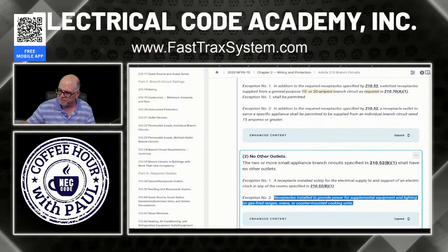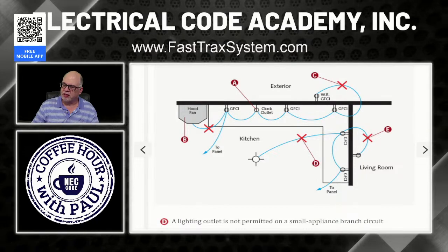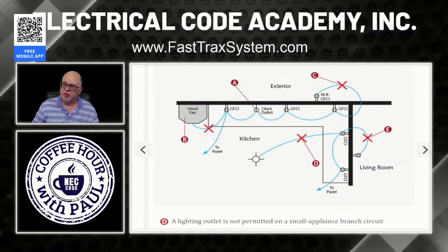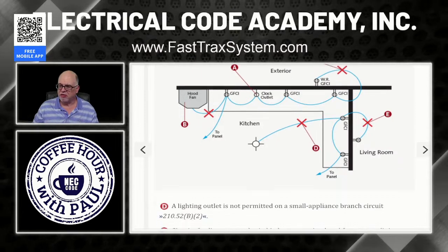So let's come back here. Also, make it really clear that, ooh, just because maybe this is a counter and it overlooks a living room, these receptacles on this side of this dividing wall are serving the living room, okay? They cannot be on the small appliance branch circuit if they're on the side and this wall is designated for the living room. It's serving that space, then no, sir. It cannot be on the small appliance branch circuit. Important to realize all that. So it's very specific for what can and cannot be on that small appliance branch circuit.